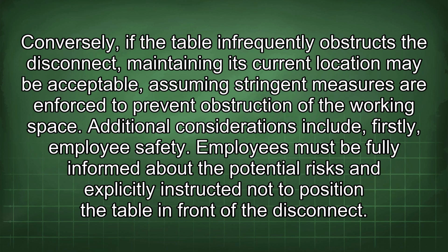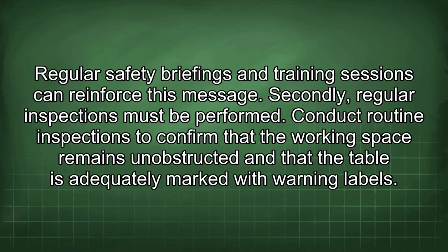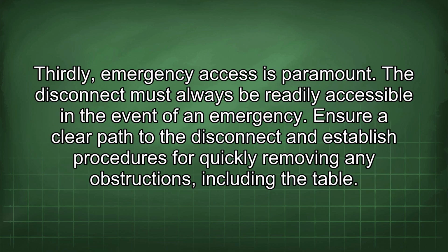Additional considerations include, firstly, employee safety. Employees must be fully informed about the potential risks and explicitly instructed not to position the table in front of the disconnect. Regular safety briefings and training sessions can reinforce this message. Secondly, regular inspections must be performed. Conduct routine inspections to confirm that the working space remains unobstructed and that the table is adequately marked with warning labels. Thirdly, emergency access is paramount. The disconnect must always be readily accessible in the event of an emergency. Ensure a clear path to the disconnect and establish procedures for quickly removing any obstructions, including the table.